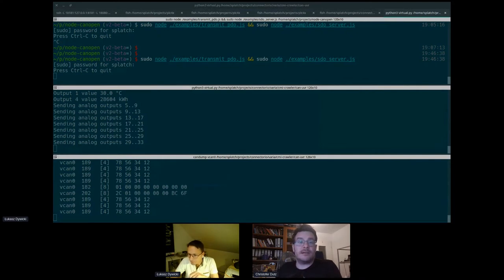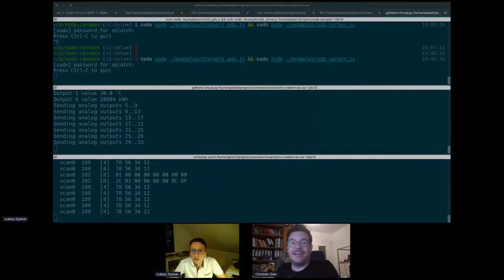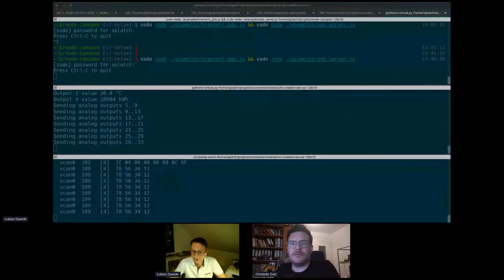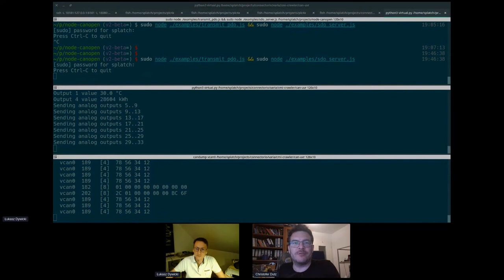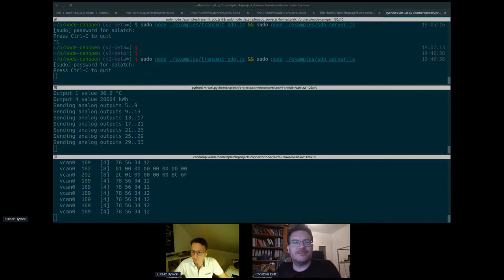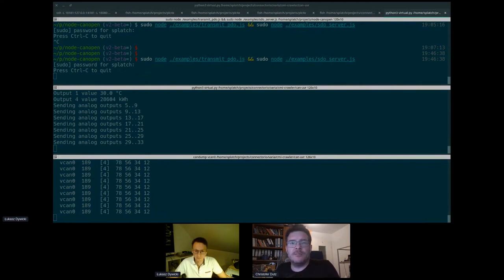One additional note on the protocols: Apache PLC4X also has support for Siemens S7 and Beckhoff ADS communication — both TCP/IP-based and vendor-specific, not standards or field buses. There are other ways to communicate with the field bus — for example, over a PLC already deployed. However, in most cases you have no access to the sources of the PLC project, so you cannot guess what the addresses are because the encoding is binary. The only reliable way to get access to the data is going over the field bus directly. If you have communication happening over Profinet, CanOpen, and so on, your IT program can tap into this communication and make sense of it.